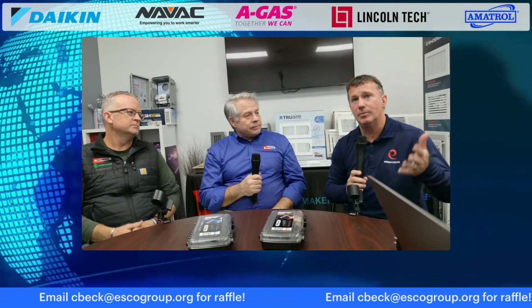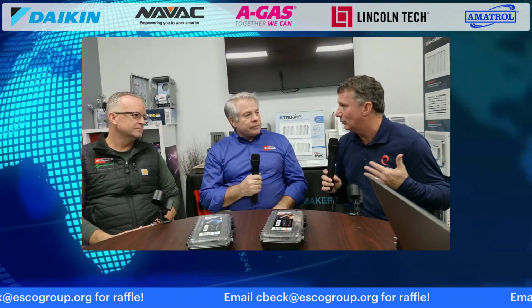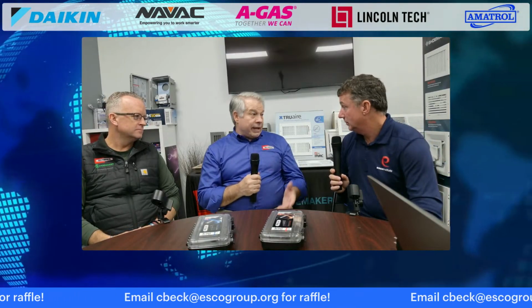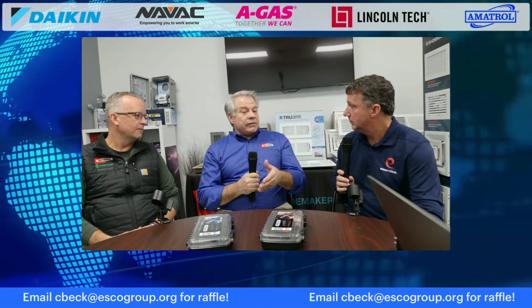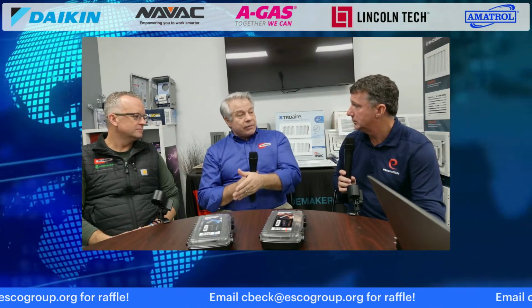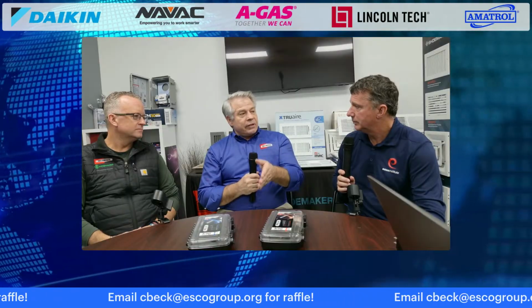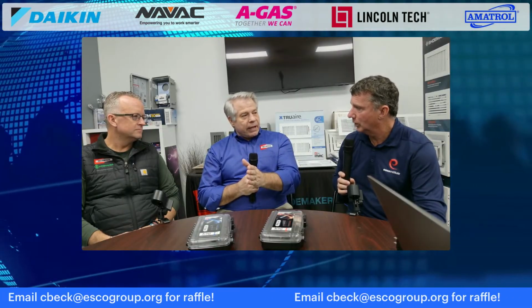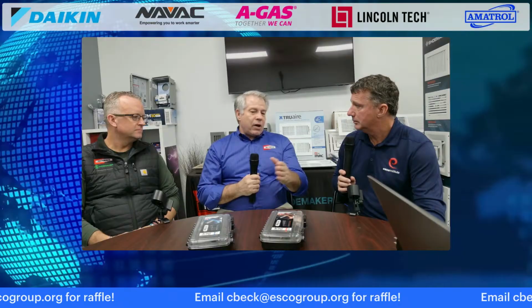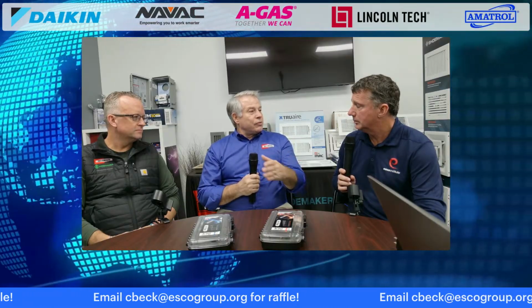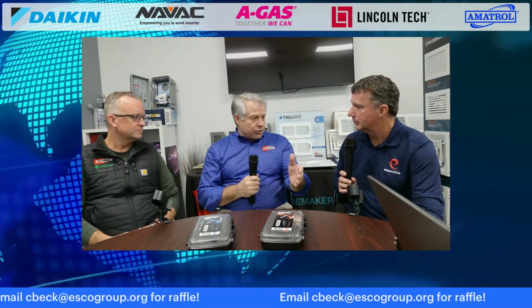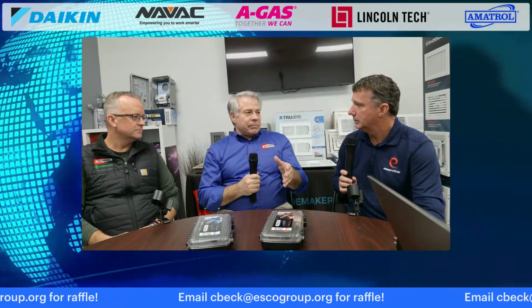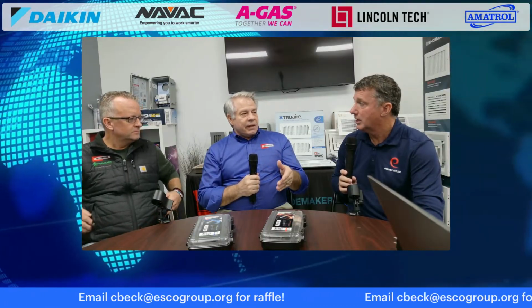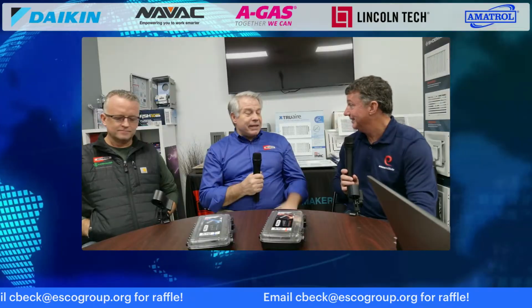We see numbers and we see ranges, but what happens when we exceed those? With higher velocity, you're going to have higher sound. That's why the 700 is up towards the upper end of the range. Going down, you'll get lower noise and less pressure drop. But that's not always good, because we want velocity. That's something we forget about.